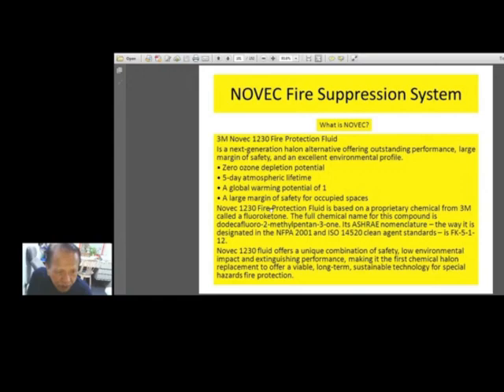Novec 1230 Fire Protection Fluid is based on a proprietary chemical from 3M called fluoroketone. The full chemical name for this compound is dodecafluoro-2-methylpentan-3-one. Its ASHRAE nomenclature. The way it is designated in the NFPA 2001 and ISO 14520 Clean Agent Standard is FK-5-1-12. Novec 1230 fluid offers a unique combination of safety, low environmental impact, and extinguishing performance, making it the first chemical halon replacement to offer viable, long-term, sustainable technology for special hazards fire protection.